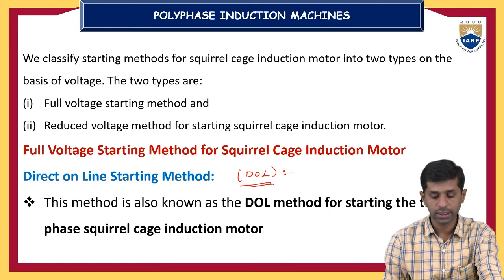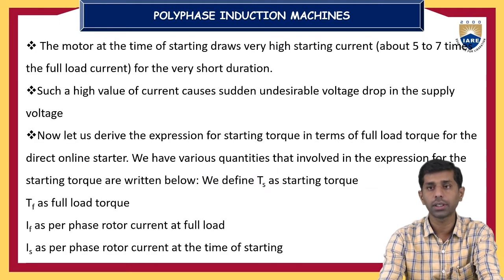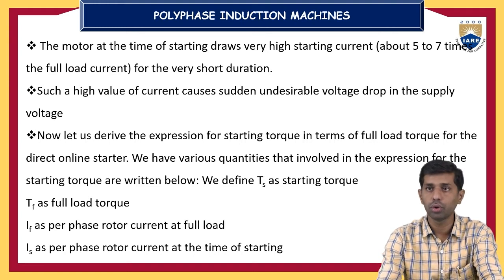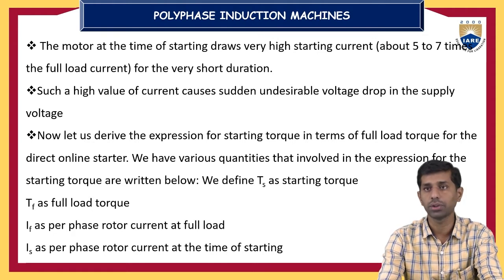So for the direct online starting method for a squirrel cage induction motor, the name itself indicates it is directly connected to the line. At the time of starting, the motor draws a very high starting current, about 5 to 7 times the full load current, for a very short duration of time. Such a high value of current causes a sudden undesirable voltage drop in the supply voltage.